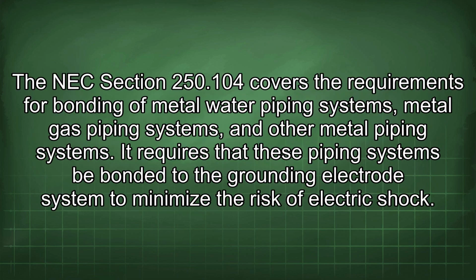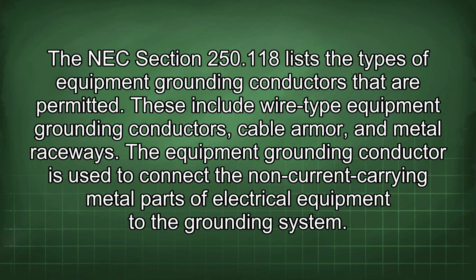The NEC Section 250.104 covers the requirements for bonding of metal water piping systems, metal gas piping systems, and other metal piping systems. It requires that these piping systems be bonded to the grounding electrode system to minimize the risk of electric shock. The NEC Section 250.118 lists the types of equipment grounding conductors that are permitted. These include wire-type equipment grounding conductors, cable armor, and metal raceways. The equipment grounding conductor is used to connect the non-current carrying metal parts of electrical equipment to the grounding system.